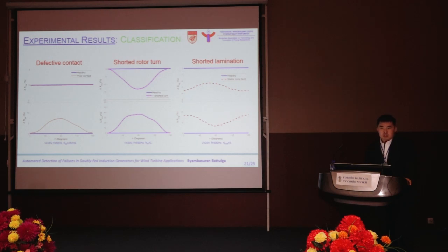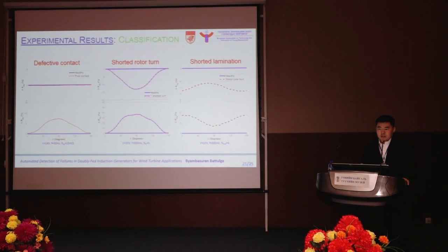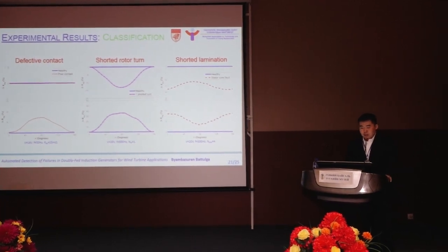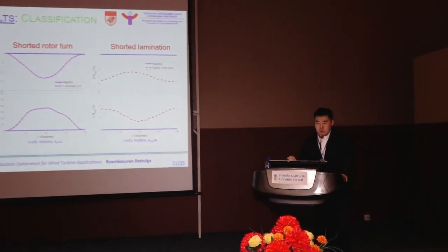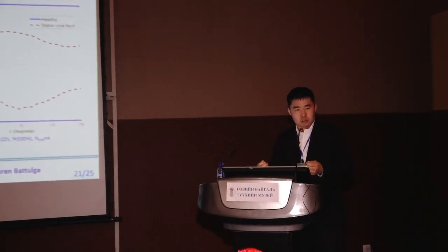And so the only reliable test method is to send a person or technician to the wind turbine, and during standby, that technician has to disconnect some rotor circuit from the system and then do some measurement. That cost is the labor of the technician, and also the transportation, especially for offshore wind turbines. Yeah. Okay, thank you.